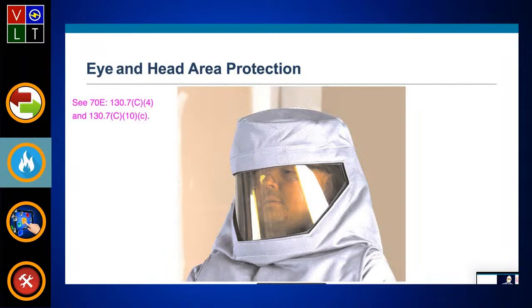So two sections have to be looked at in 70E to understand this. If I just looked at 130.7C4, no, I don't need safety glasses underneath that shield. But if I go over and read the second section, they work hand in hand together, and look at 130.7C, 10C, it says yes, you do need safety glasses as well as your shield, where it's a hood or a safety shield, whatever, you need your safety glasses under it. So make note of those two.